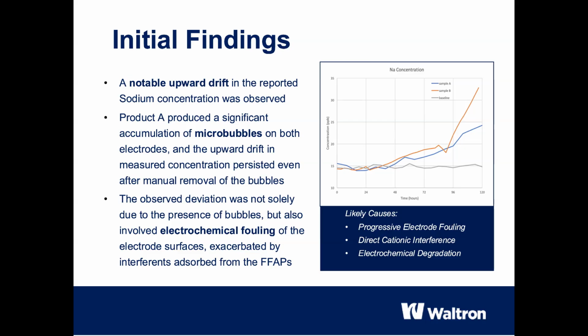Our analysis led us to 3 likely and mutually reinforcing causes. 1. Progressive electrode fouling. The surface-active FFAs build up over time as a thin film on the electrodes. This layer acts as a barrier and distorts the electrical potential. 2. Electrochemical degradation. The microbubbles are a symptom of the electrochemical degradation of the amines directly on the electrode surface. This creates new interfering substances that further accelerate contamination. 3. Direct cationic interference. The positively charged amine molecules are mistakenly detected as sodium ions by the sodium sensor. This leads to a positive measurement error. In summary, the analyzer is no longer measuring sodium, but is reacting to the chemistry of the FFAP itself.